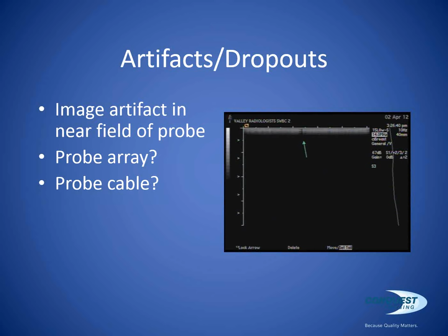One of the ways to tell if you have a bad cable is you can activate the Doppler function, and when the Doppler is on, you can hold the transducer by the strain relief up near the scan head and slowly flex the scan head back and forth, kind of rotate it around in a circle in each direction. And if you induce noise within that Doppler signal, you know that you have broken cables within that neck.